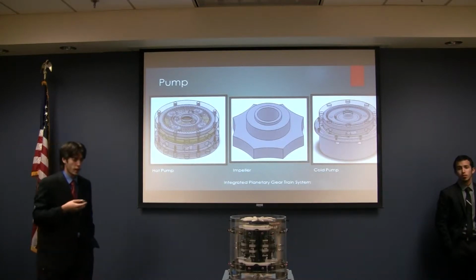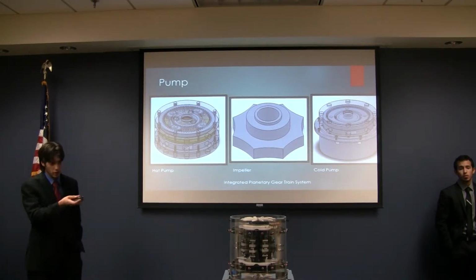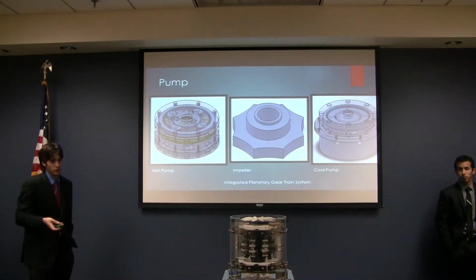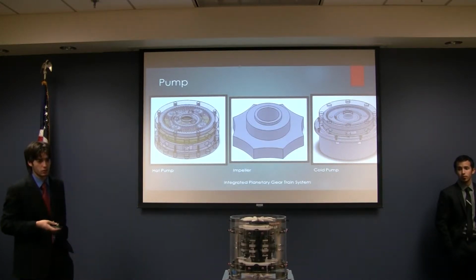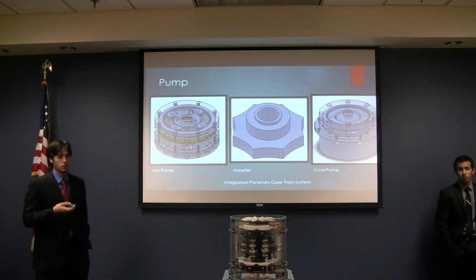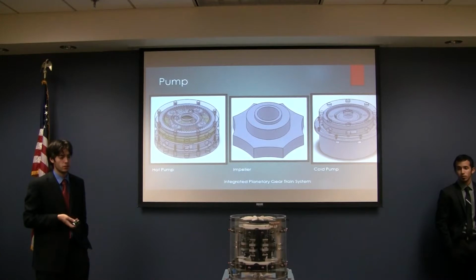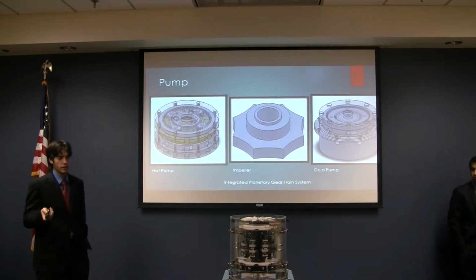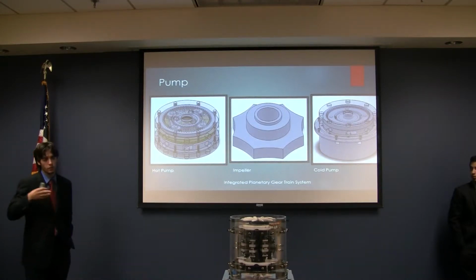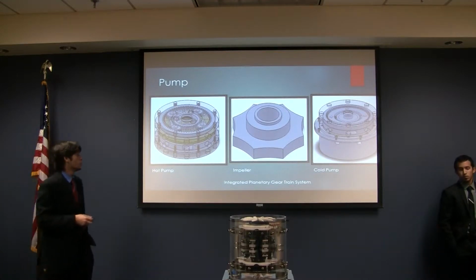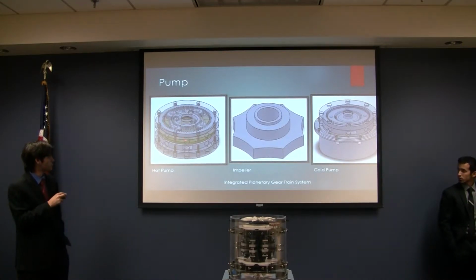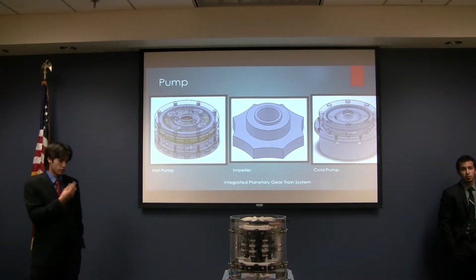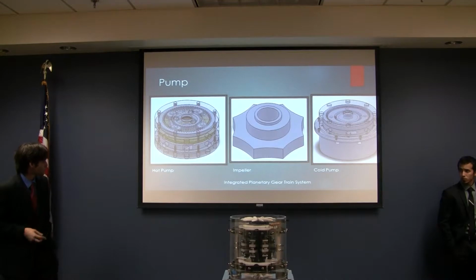The reason we had to design the pump is that, due to the design constraints and the size, we couldn't find any pump that would fit in there and perform the job we needed. Also, there are 16 total heat exchangers, 8 of them on the hot side. At any given time, the flow in any of the heat exchangers cannot touch each other. You can't mix the heat because one may be on the cold cycle and the other on the hot cycle. So we had to have inner channels that distribute the flow from one inlet to the other outlet, but at the same time do not mix from one to the other. That's another reason why we had to design custom pumps as well.